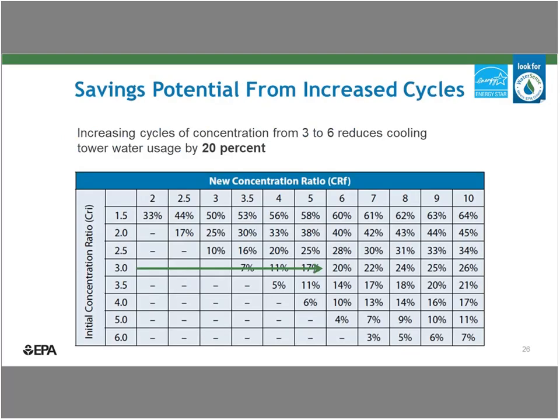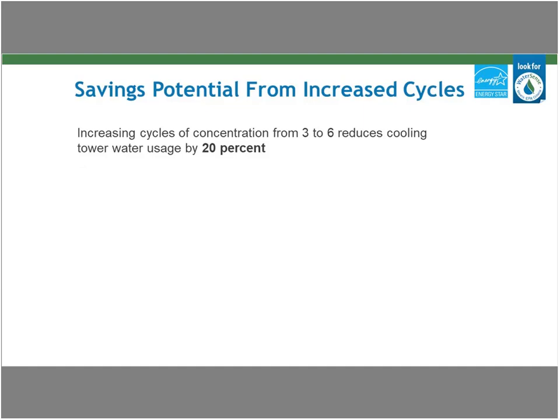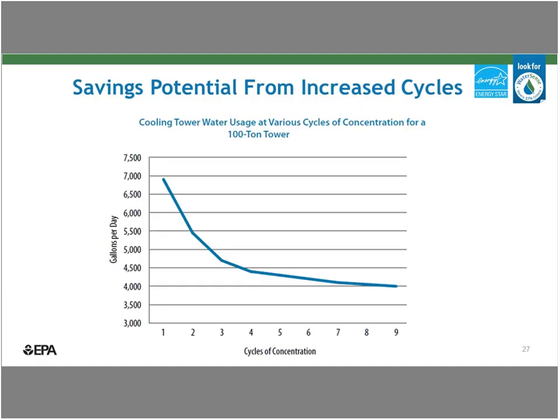This chart here shows the type of savings that you can achieve by increasing your cycles of concentration. So read the initial cycles on the left and across to the new cycles along the top. For example, improving the cycles from 3 to 6 would provide a 20% reduction in your cooling tower water use. So you can see how significant the savings can be if you increase cycles.